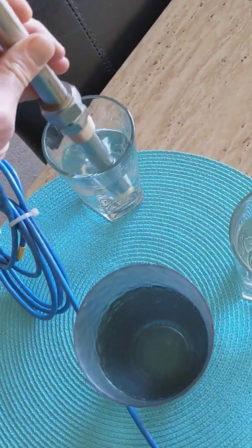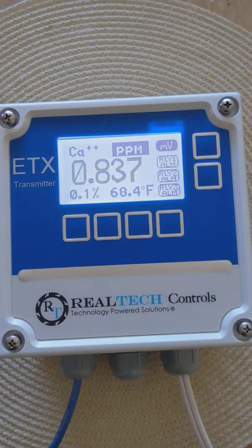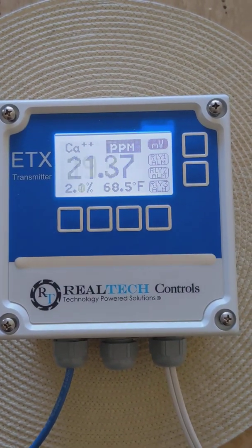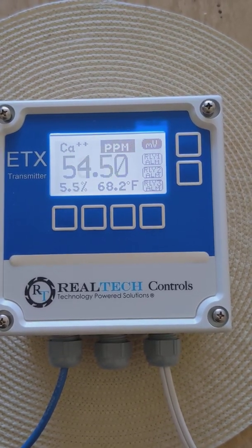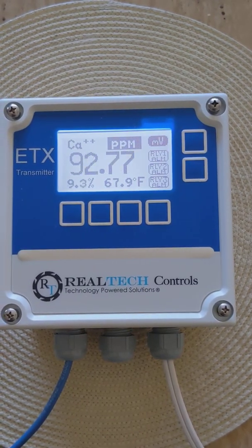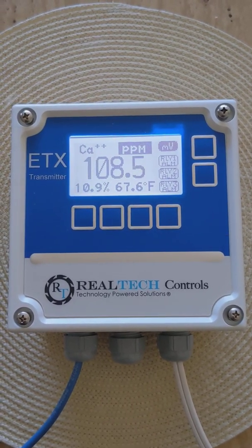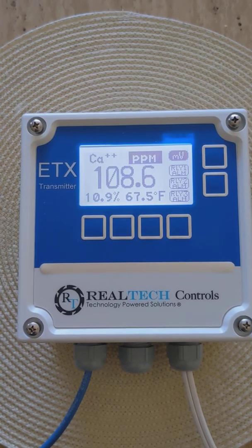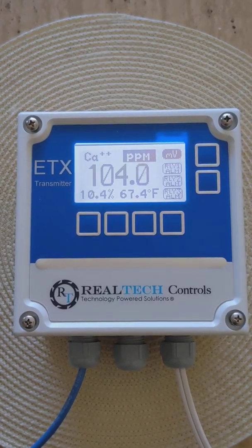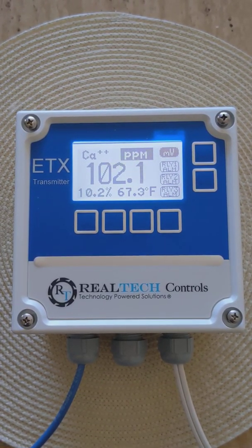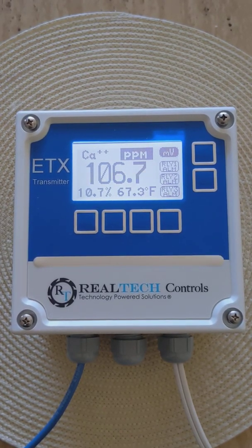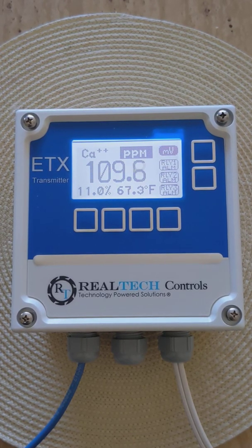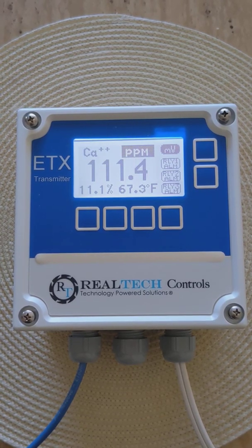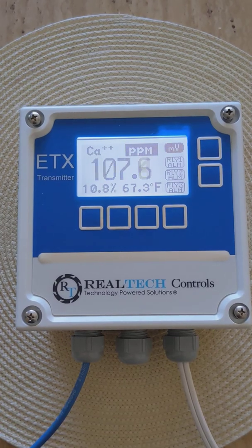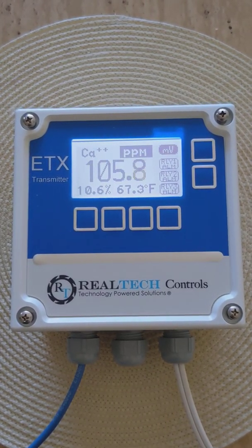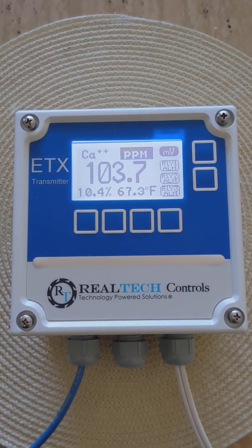I'll use it again in my solution, which I've said is 100 ppm. We'll see how the repeatability of this unit works out. It's always hard to get flow to stabilize the unit, but you can see it dropping close to 100. And the fluctuation is just because I've got it swirling in a cup. But that is the 0 to 100 calibration, 2-point calibration on the model ETX Water Hardness Analyzer.